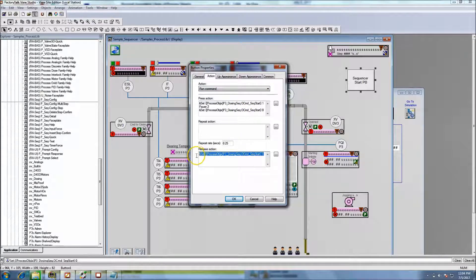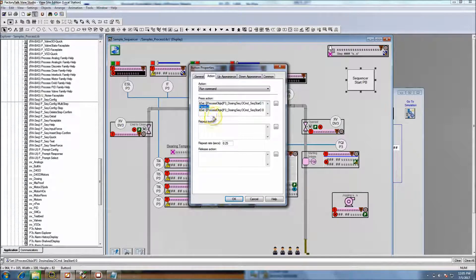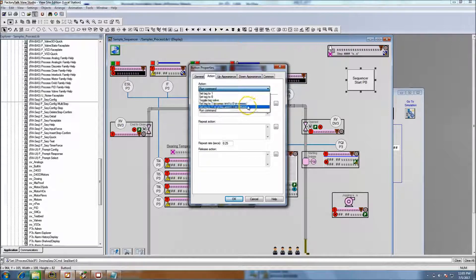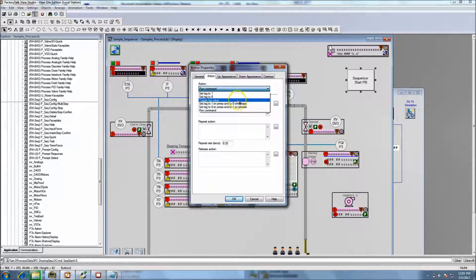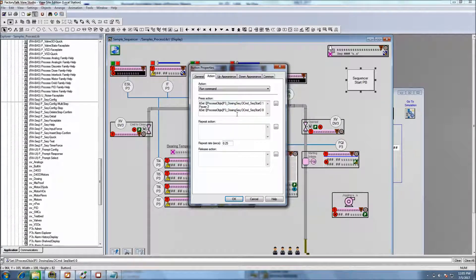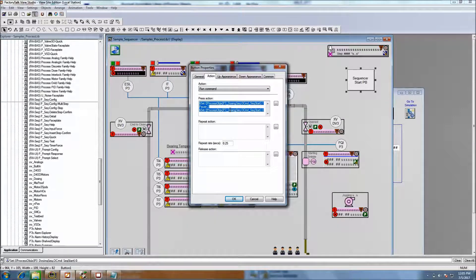Here's the thing - with a run command you get control over that set and release. You can time it with a pause and control exactly when you do the release if you have a lag. If you just say set one then release to zero, it's going to do that instantaneously, so you're relying on your system being absolutely perfect. In this day and age we know there's variability in just about everything, so this is probably the best way I've seen to minimize any kind of risk.